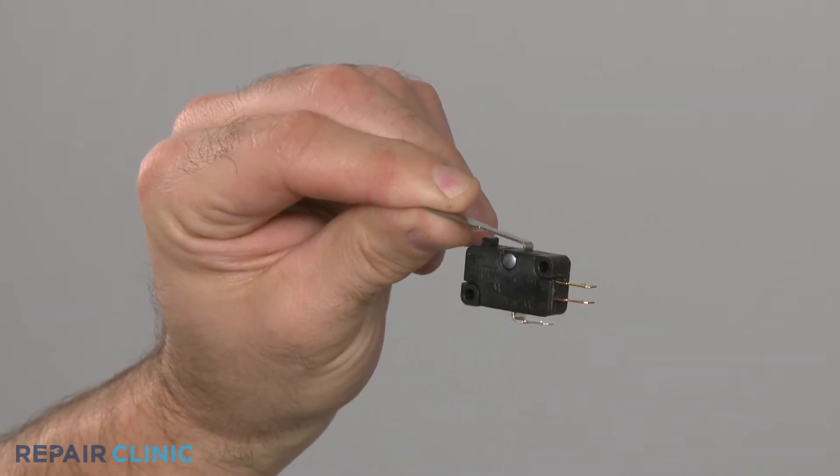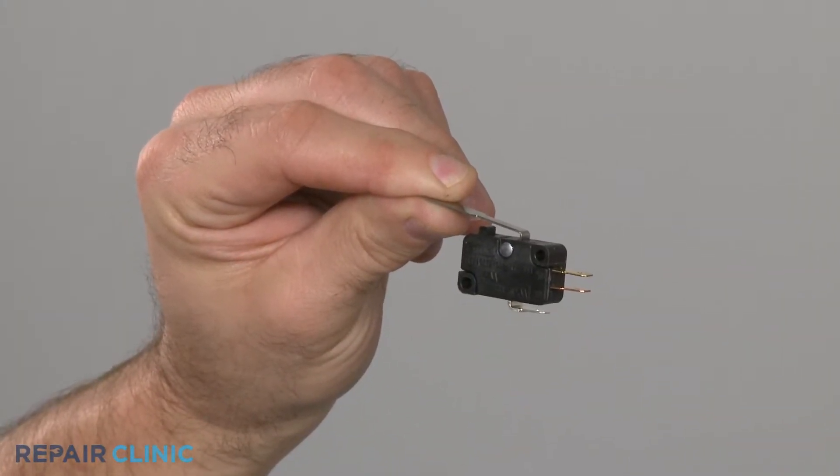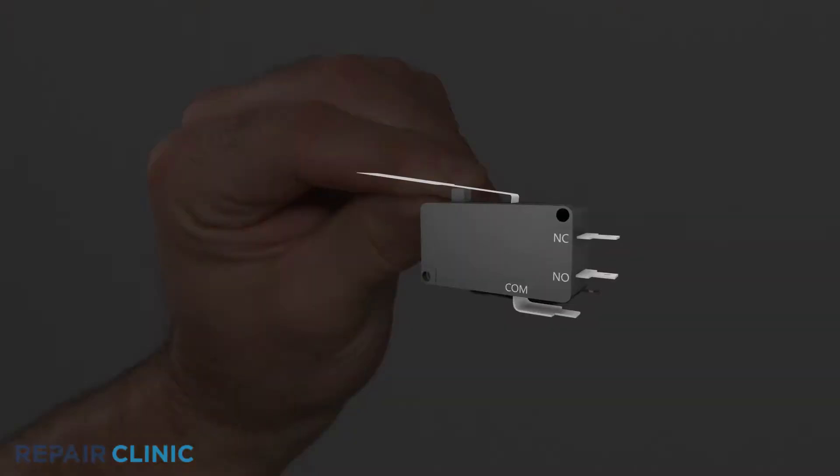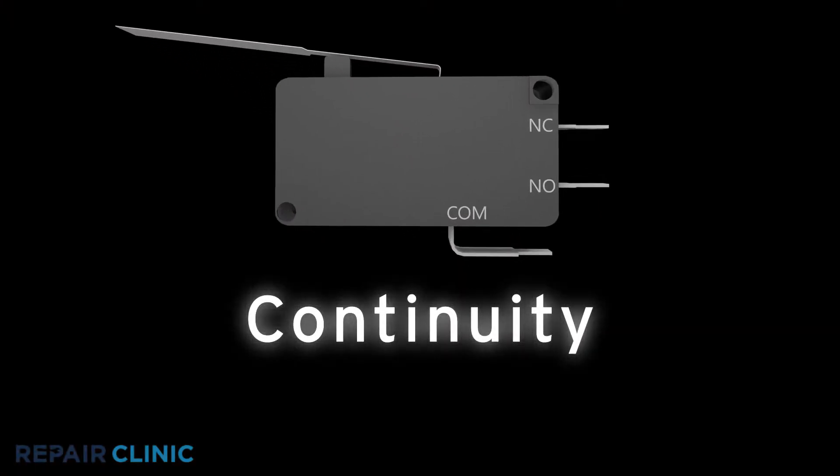Since you can't always tell if a switch has failed simply by looking at it, you'll need to perform a continuity test. A continuity test will determine if a continuous electrical path is present in the switch.